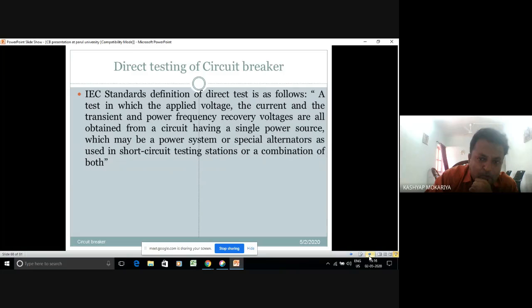IEC standards definition of a direct test is as follows: a test in which the applied voltage, the current, and the transient and power frequency recovery voltage are all obtained from a circuit having a single power source. A big definition: all is obtained from a single power source.